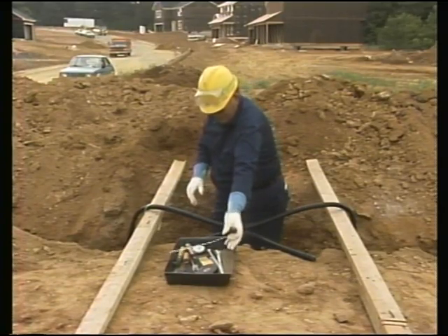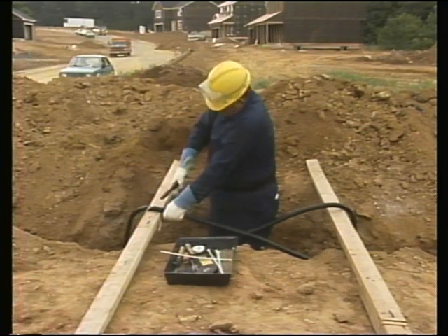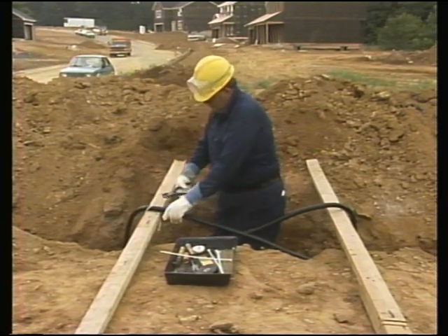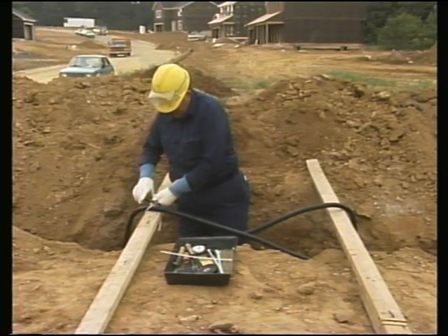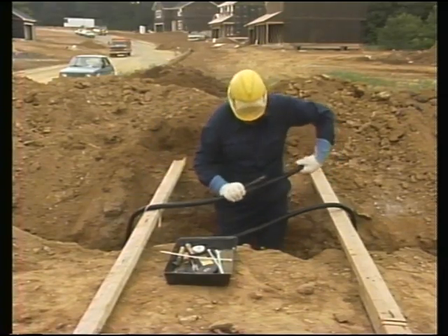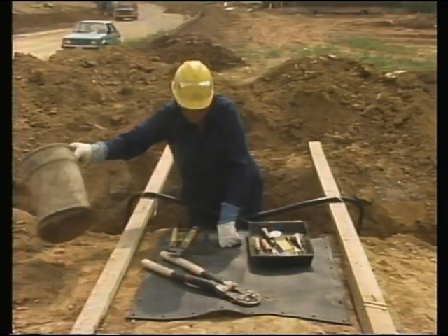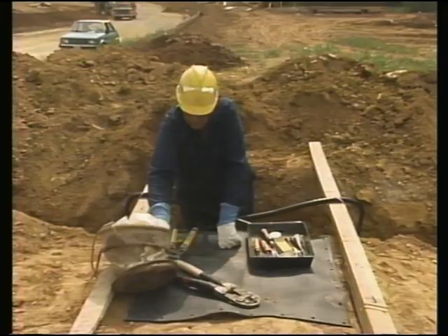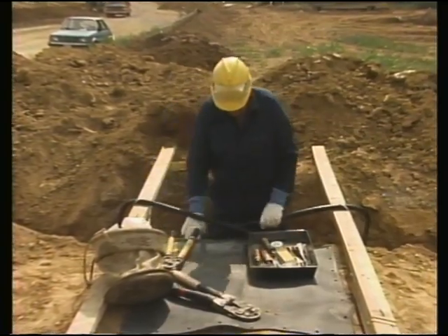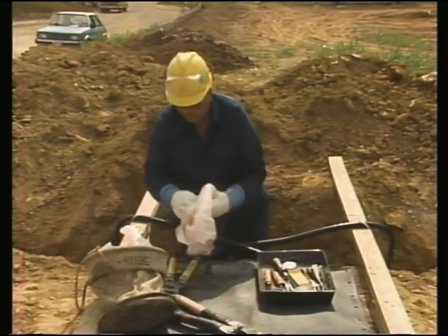Finally, training the cable before making the final splicing cuts should help reduce the chance of moving the conductor after cutting it. Moving the conductor after cutting it can cause conductor strands to become uneven, causing a weak point in the conductor splice. The other part of preparing for the splice is making the final cut of the cable ends. This involves making precise measurements and following the directions carefully.